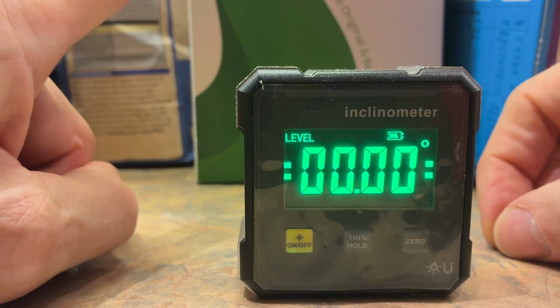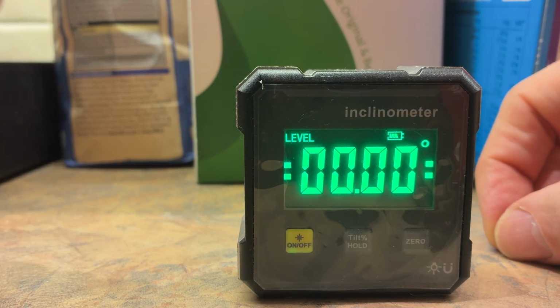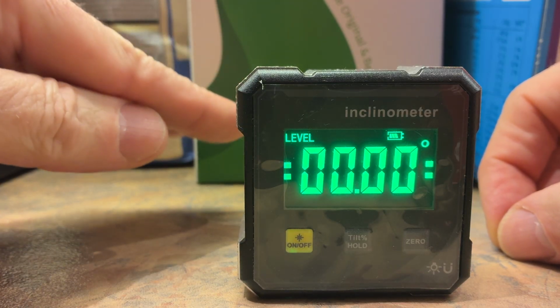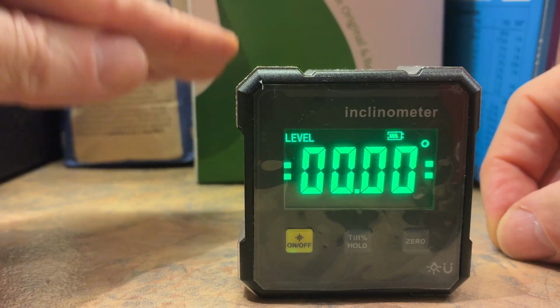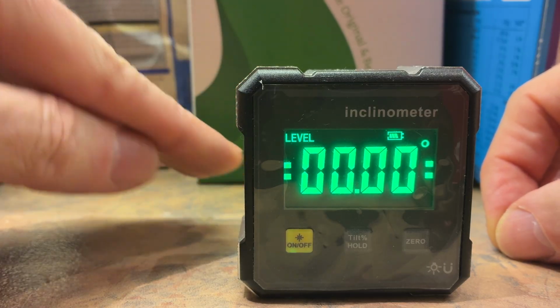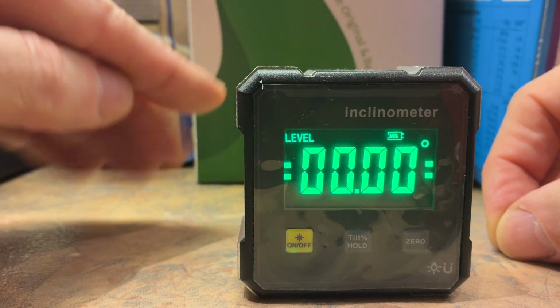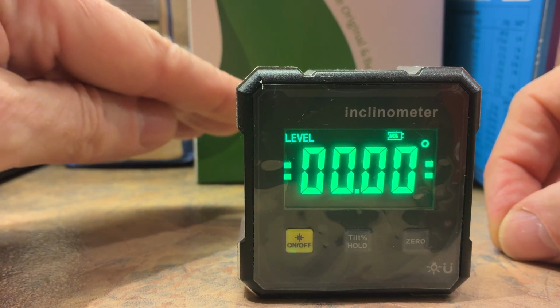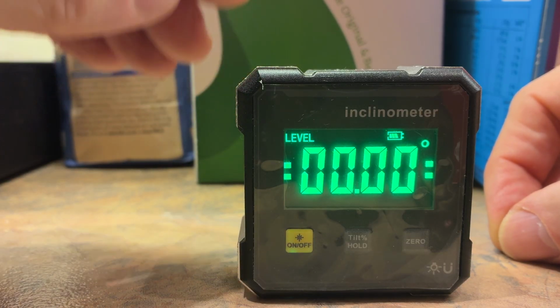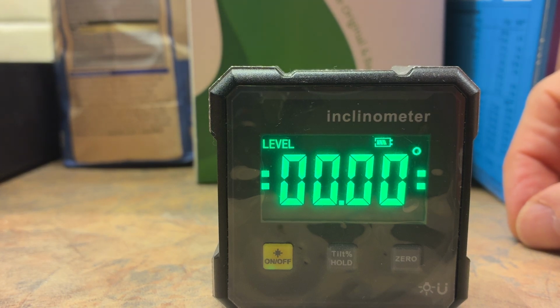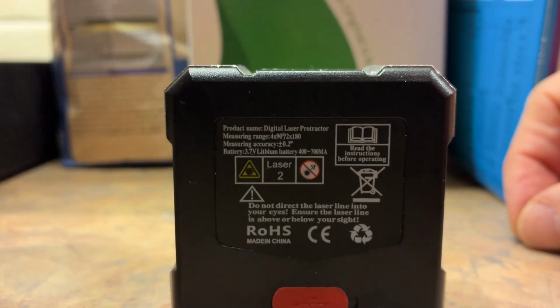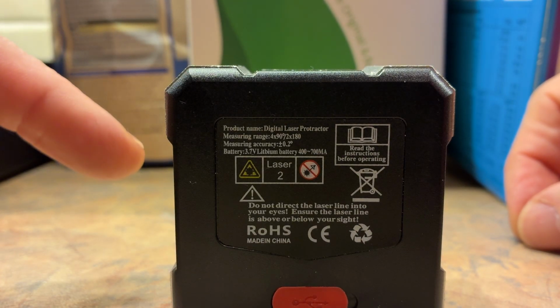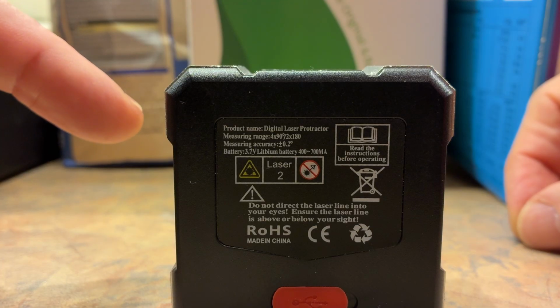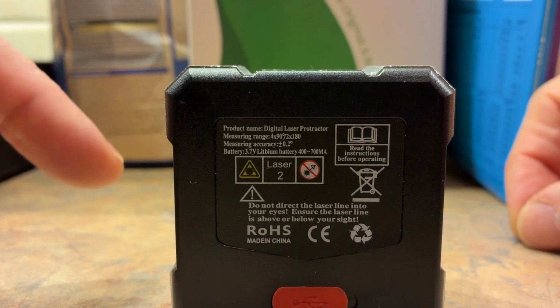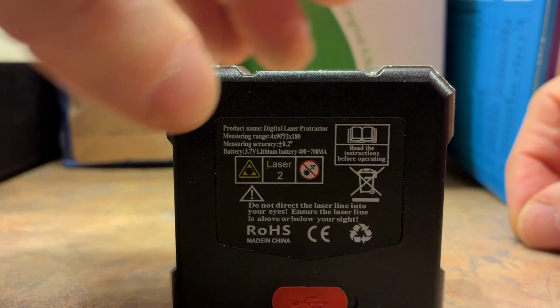Right, now, the one thing that's different about this device compared to some is that it's absolutely important when you calibrate it that you have an absolutely level surface, because it zeroes itself on the surface and it relies on it being level. Now, you can test whether or not you've calibrated it accurately, because that device now is saying 0. If I turn it round, it should still read 0. If it doesn't, you've not calibrated it properly, because the surface that you used to calibrate it on wasn't flat.